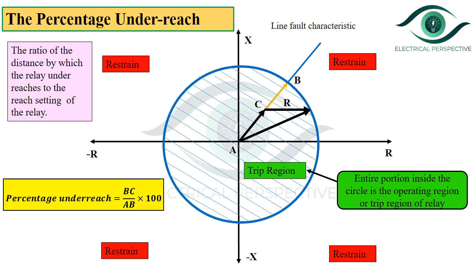Now let us see what is percentage underreach. It is the ratio of the distance by which the relay under-reaches to the reach setting of the relay. From the figure, percentage underreach = (BC / AB) × 100, where BC is the distance by which the relay under-reaches and AB is the reach setting of the relay.